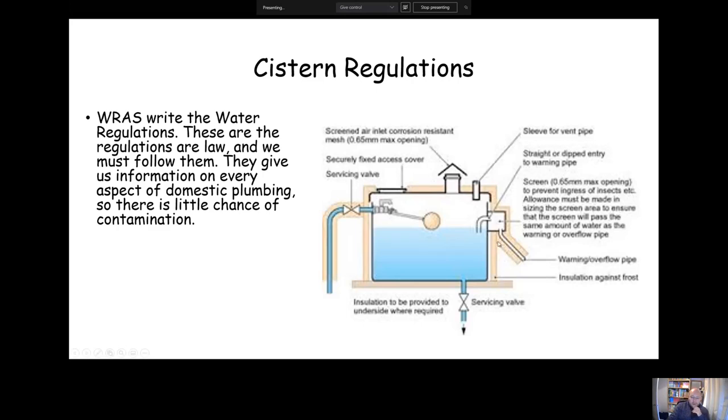We must always have a screened overflow in case the inlet control device, the float valve, fails. That would allow water to flow out of the system and stop it from overflowing and ruining your house. We'd also have an automatic means of water control, which would normally be a float operated valve. Before a float operated valve, we must always have a means of isolation, a service valve, so we can maintain the float valve if needs be. We also must have a securely fixed, tight fitting lid so we can access for cleaning and maintenance of the float valve.